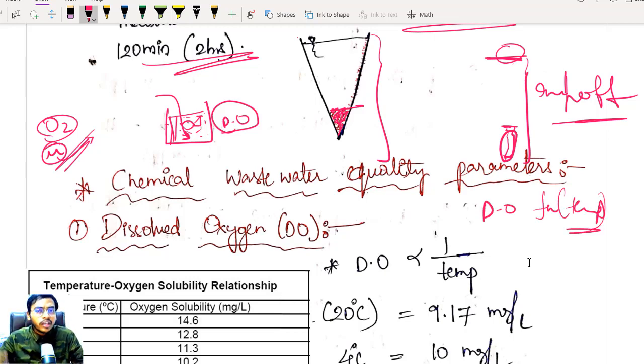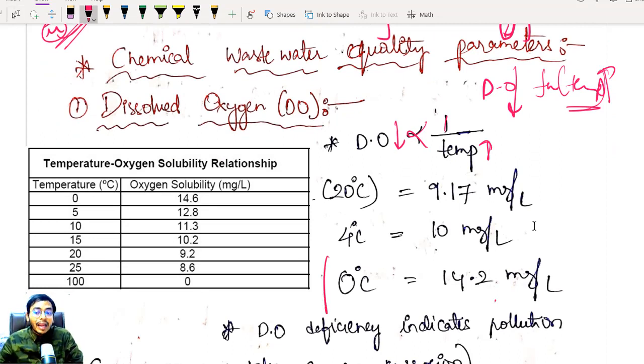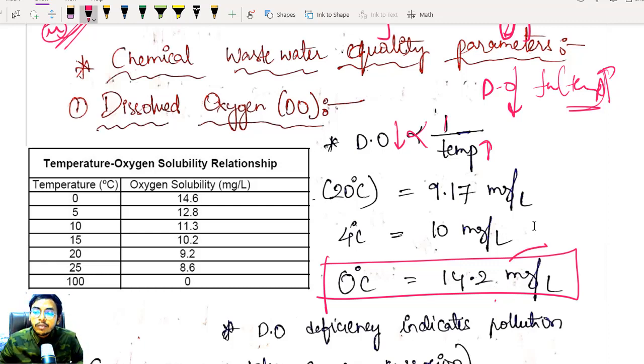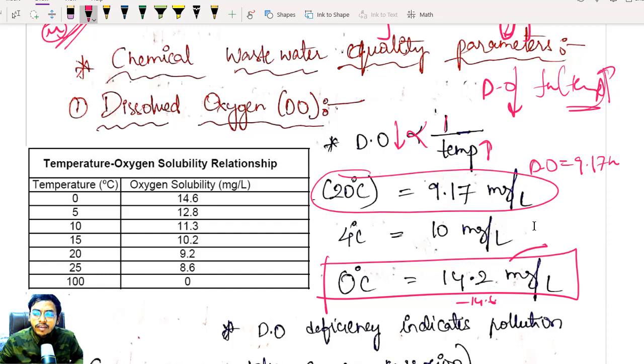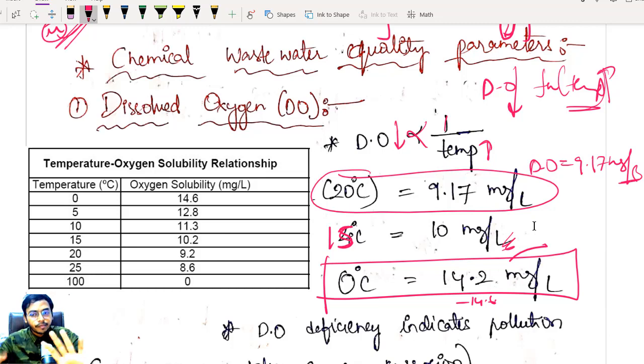Dissolved oxygen is a function of temperature — very important. If temperature is more, my dissolved oxygen will be less; they are inversely related. Key values to remember: at 0°C, DO saturation is 14.2 to 14.6 mg/L. At 20°C, DO saturation is 9.17 mg/L, roughly 9.2 mg/L. At 15°C (the standard temperature used in most of the western world), DO is around 10 mg/L. Remember these three values for objective examination purposes.